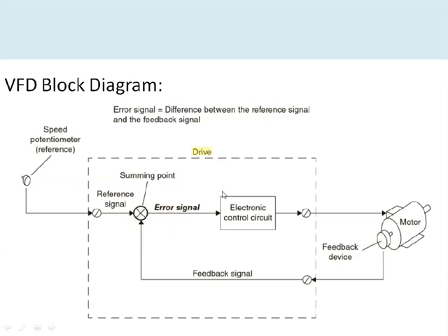The drive sends signals to the motor, and to confirm whether the motor is rotating at the desired speed, a feedback signal is required. This can be taken through an encoder or a tachometer. The actual speed and the reference speed are compared, and the drive issues further commands to the motor to increase or decrease its speed accordingly.